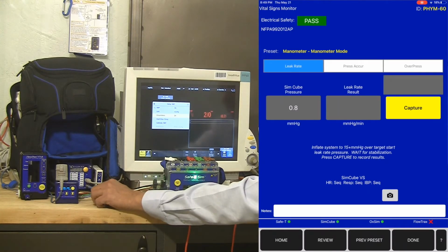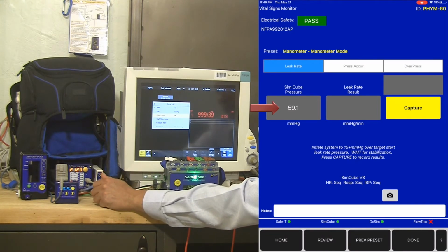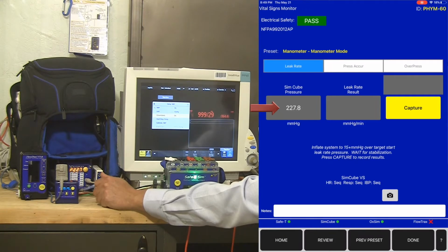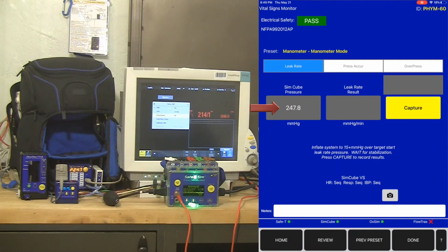So I'm going to inflate the system to about 240, and I can see on my app that it is tracking the pressure of the SimCube. Here's about 240. And so I can see my real-time SimCube pressure right on my iOS device, and it's going to start calculating a leak rate. So we've got now a leak rate result in this box.